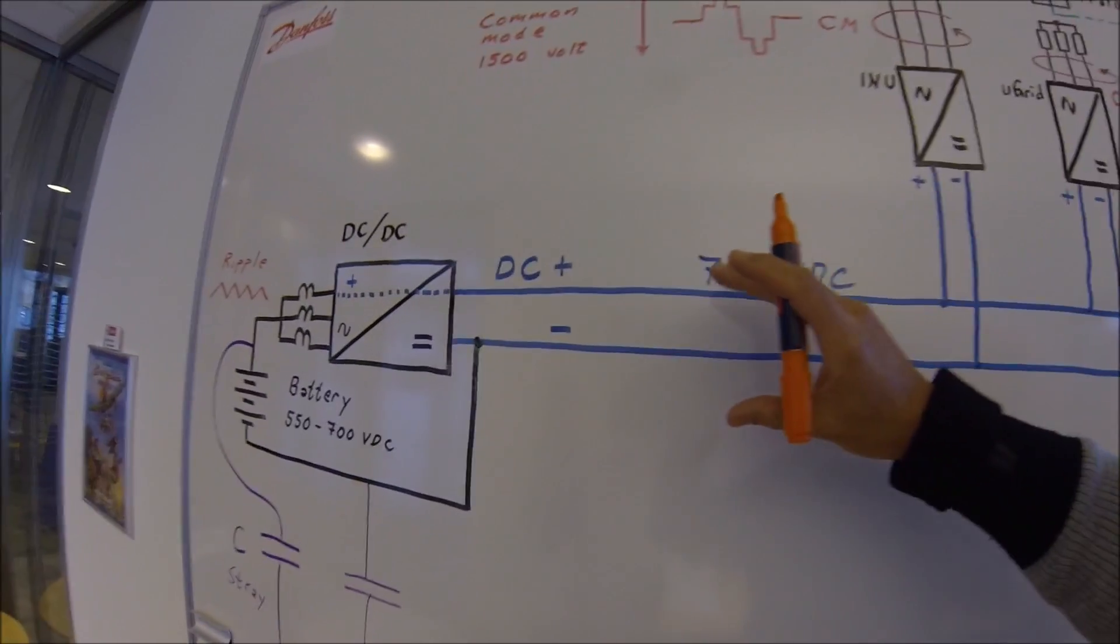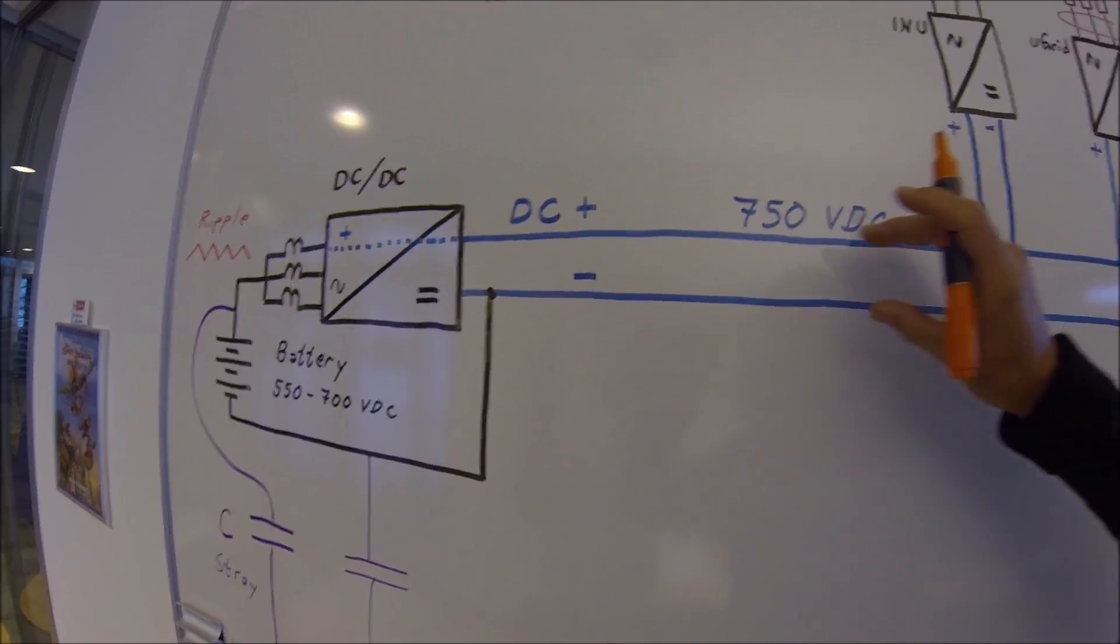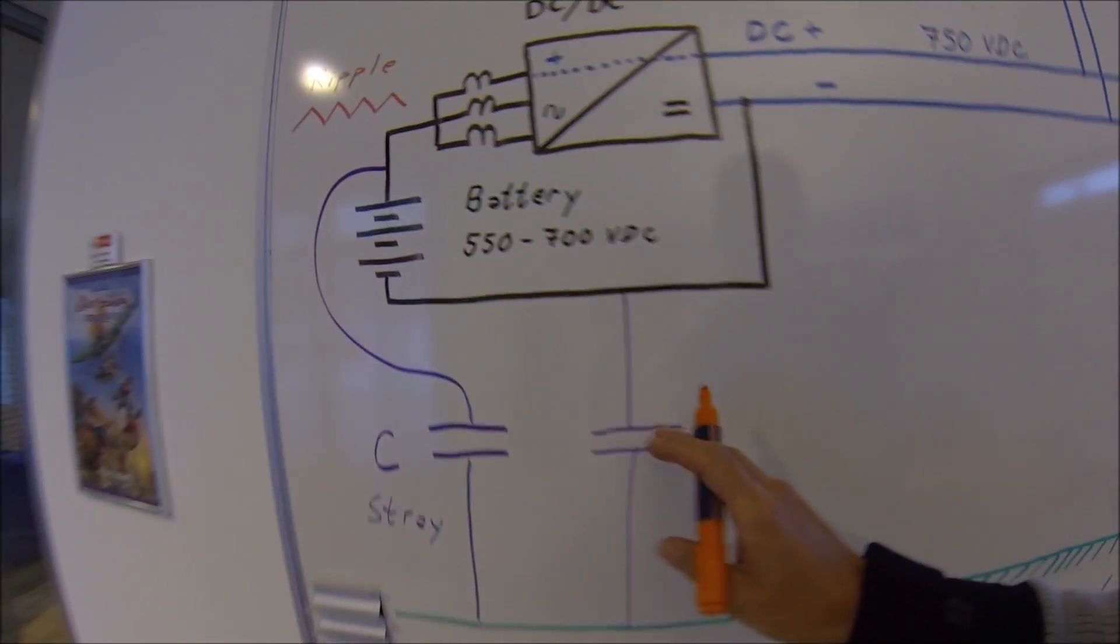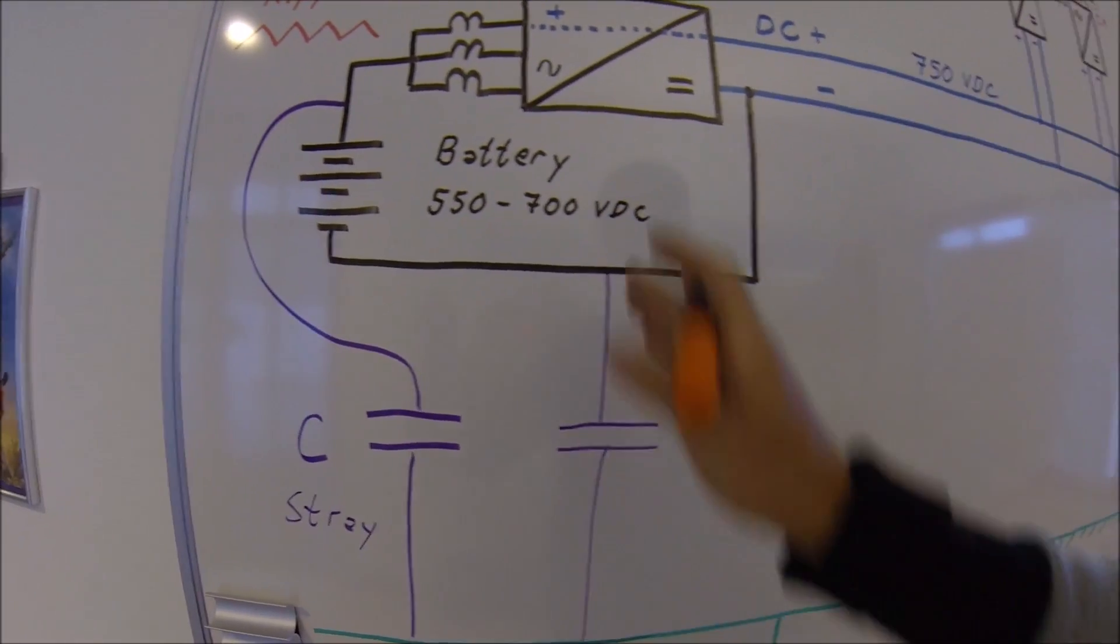Then we have to make sure that our DC bus is totally stable compared to the protective earth. We already know there is a stray capacitance here, so there is a connection here.